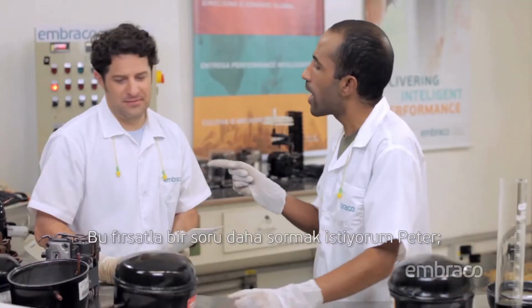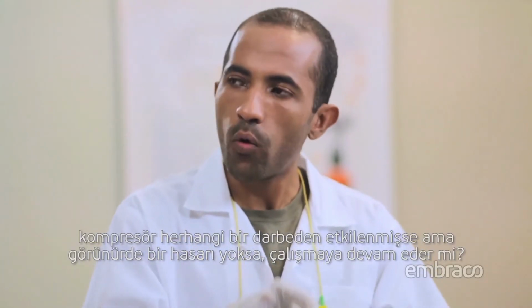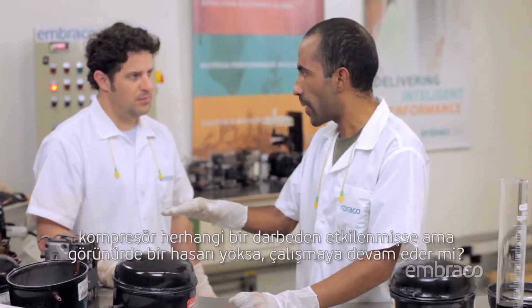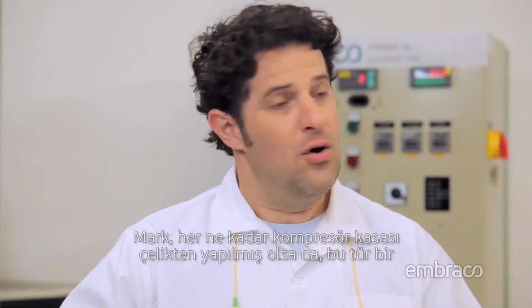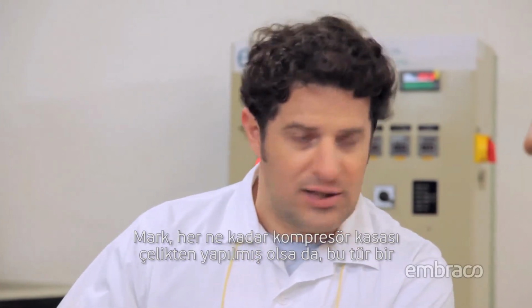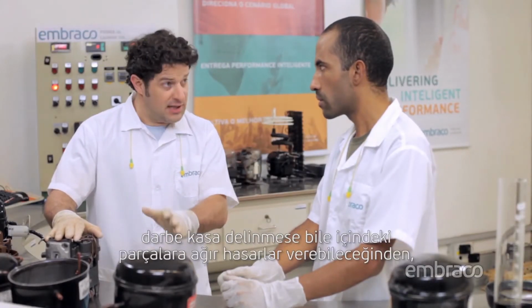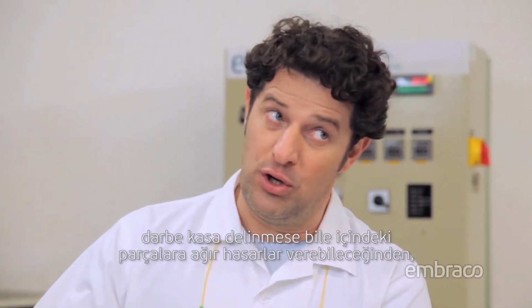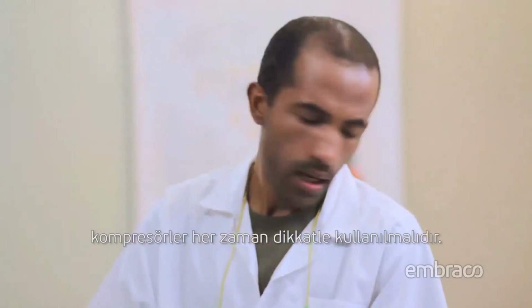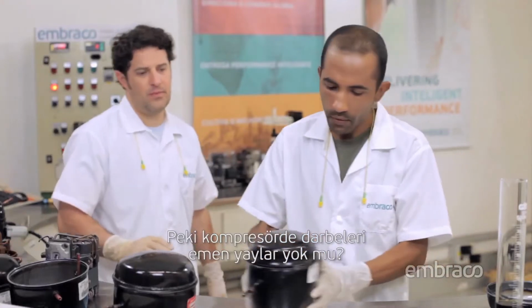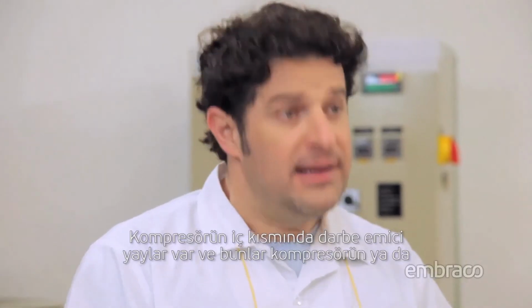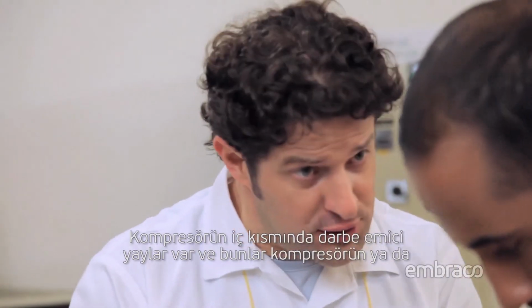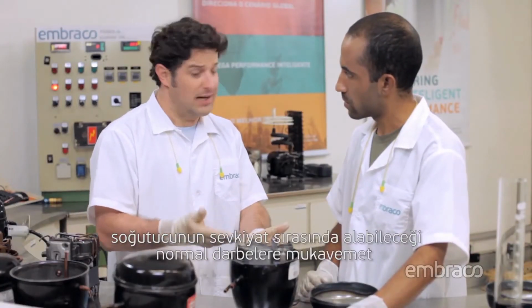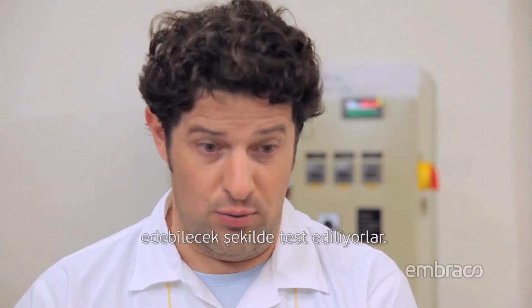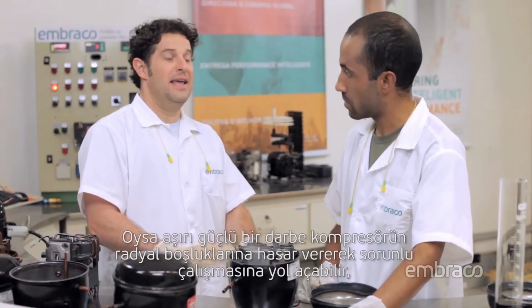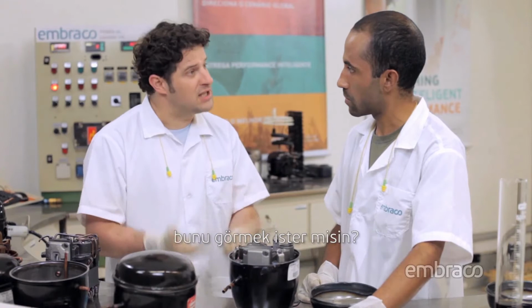Yes. Taking advantage of this opportunity, Peter, if the compressor suffers some impact but doesn't show any apparent damage, does it still work? Mark, although the housing is made of steel, the compressor should be treated with care, since the impact can cause severe damage to internal components, even if the housing isn't dented. But doesn't the compressor have springs to absorb impacts? Internally, the compressor has shock absorption springs and is tested to withstand normal shocks during shipment of the compressor or refrigerator. Now, excessive impact may damage the compressor's radial clearances, causing it to not work properly.